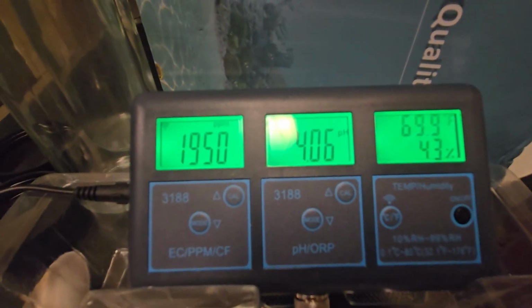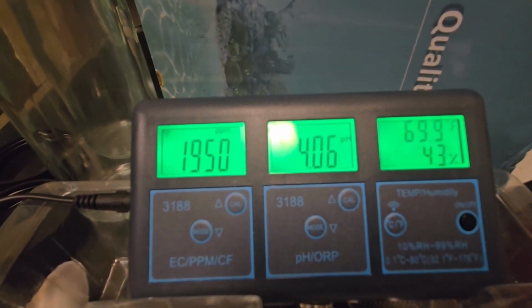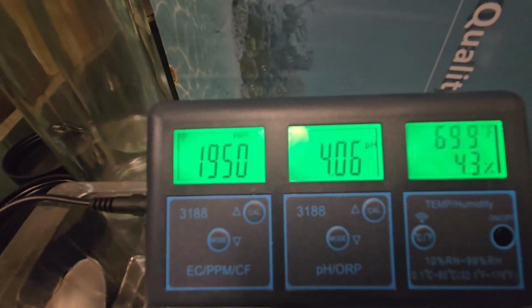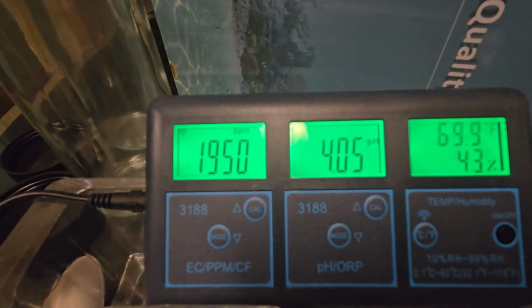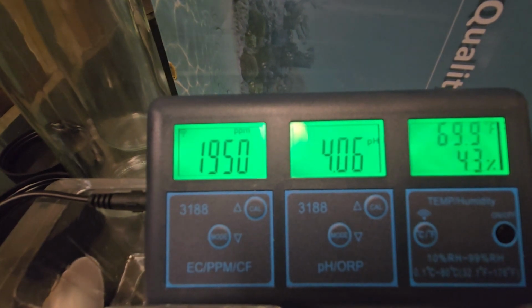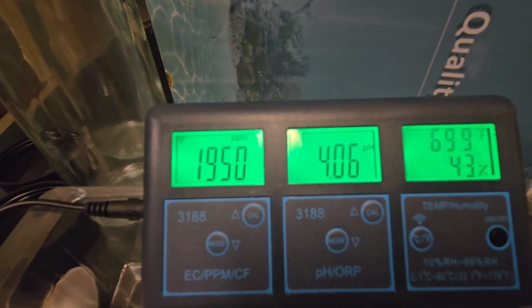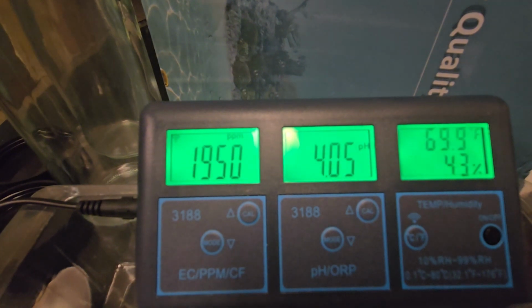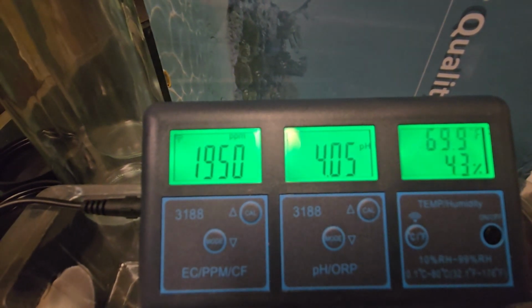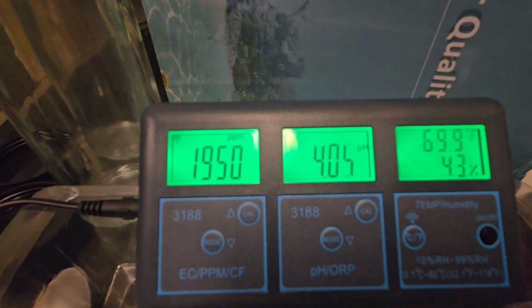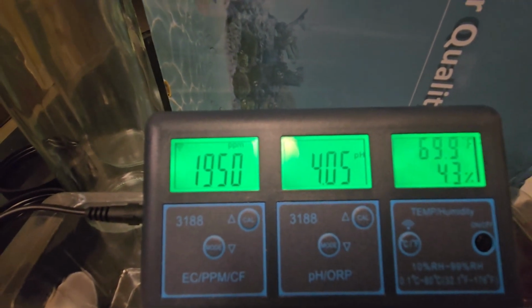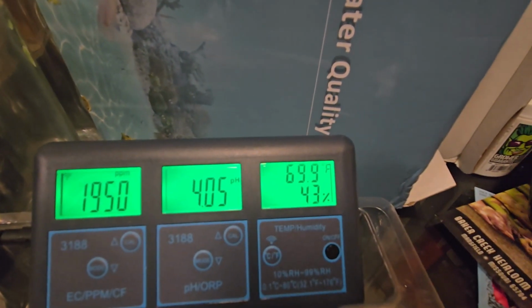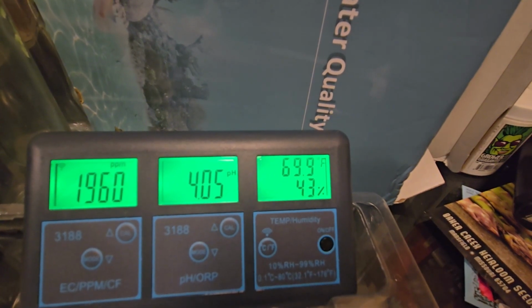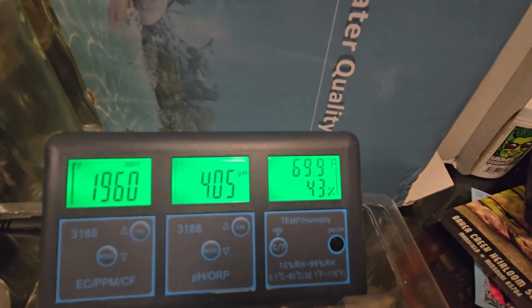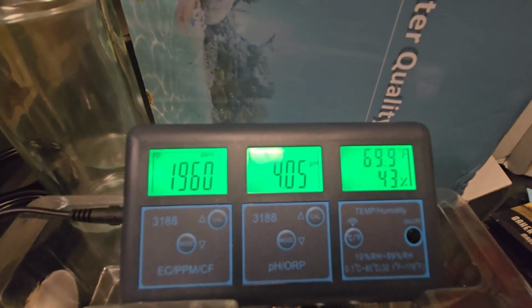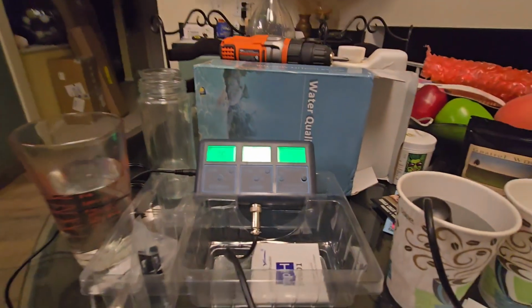So it's saying that we have EC or PPMs at 1950, which is beyond me because the only thing in these cups are water and the calibration solution. The 4.05 or 6 isn't far off, so that could be the water here from my tap influencing that, which I know comes out of the tap at about 7.0. Water at 69.9 degrees, and they're saying that there is 43% relative humidity in the room. How it knows that is beyond me.